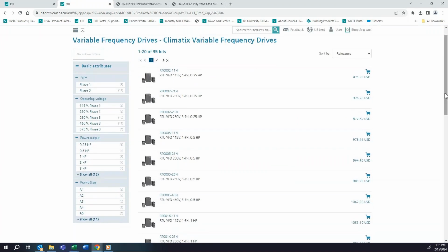These VFDs, if you remember about 10, 15, 20 years ago, the term micro drive came out in our industry. Very small footprint compared to a normal drive or a VFD without the word micro drive in front. But those micro drives, because of their footprint and the real estate that they require, do not have a contactor bypass built in. That's a big difference between a micro drive and a drive like a Danfoss full-blown drive, right?